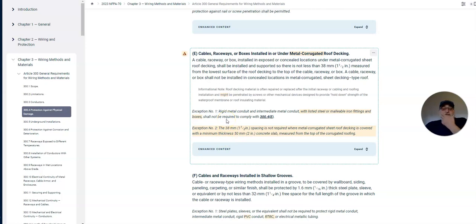We got two exceptions. Let's look at these right quick. Rigid metal conduit, intermediate metal conduit with listed steel or malleable iron fittings or boxes shall not be required to comply with 300.4(E). Rigid metal conduit or IMC with listed steel and malleable iron fittings. So if you're using rigid, you can put that up there, but if you're using EMT, you can't.